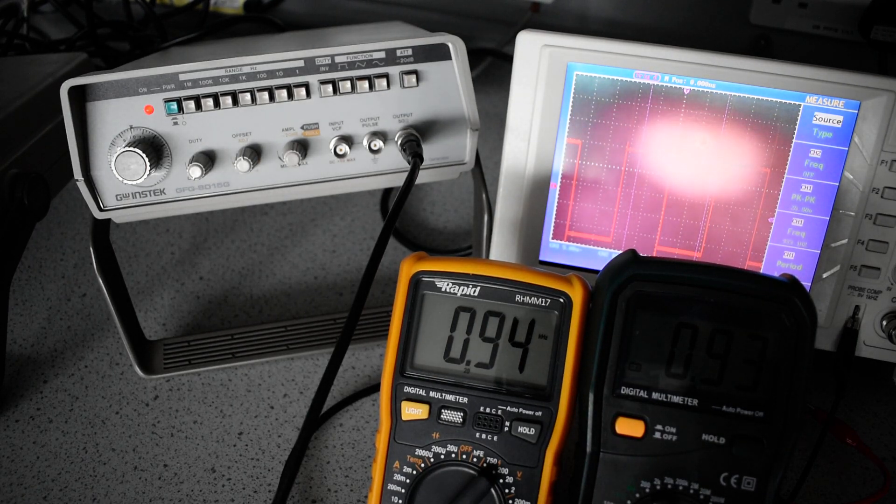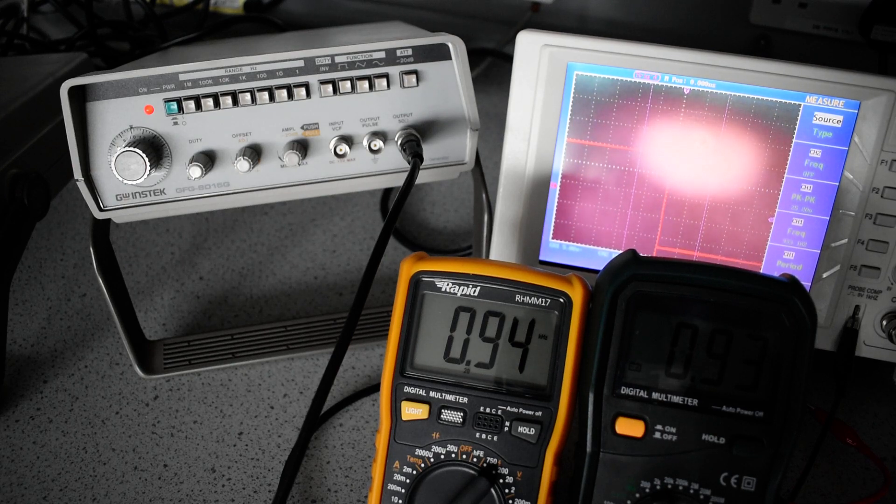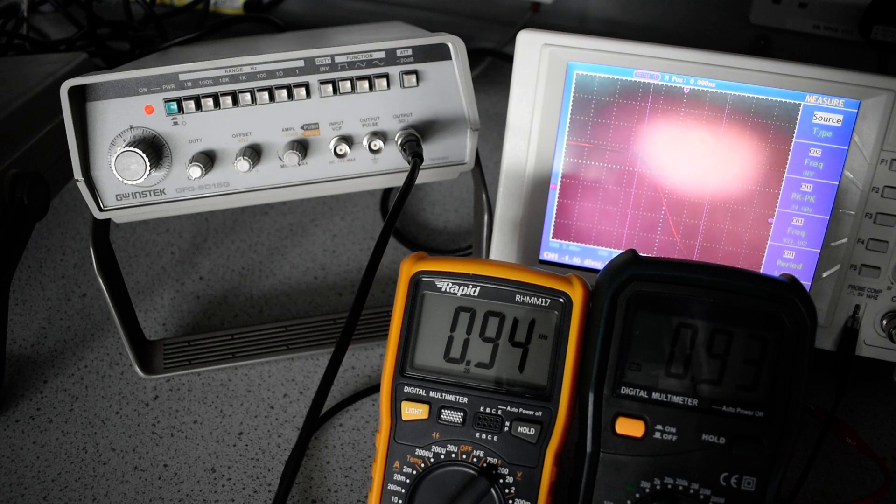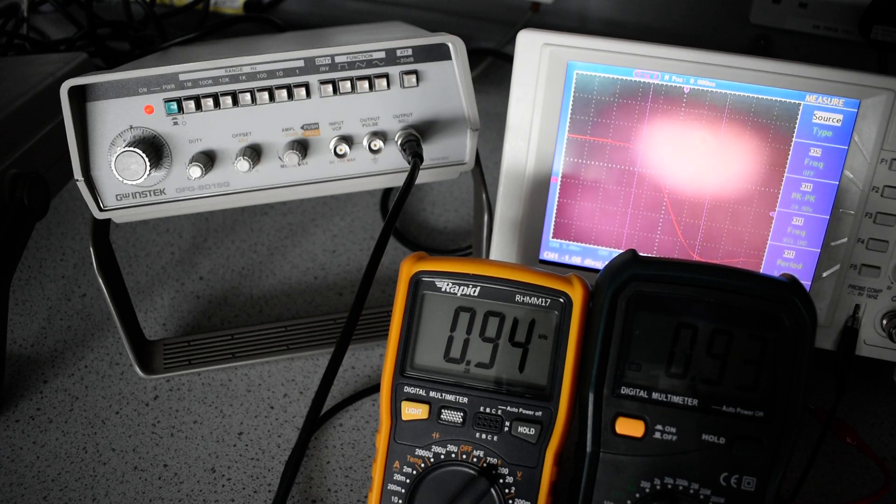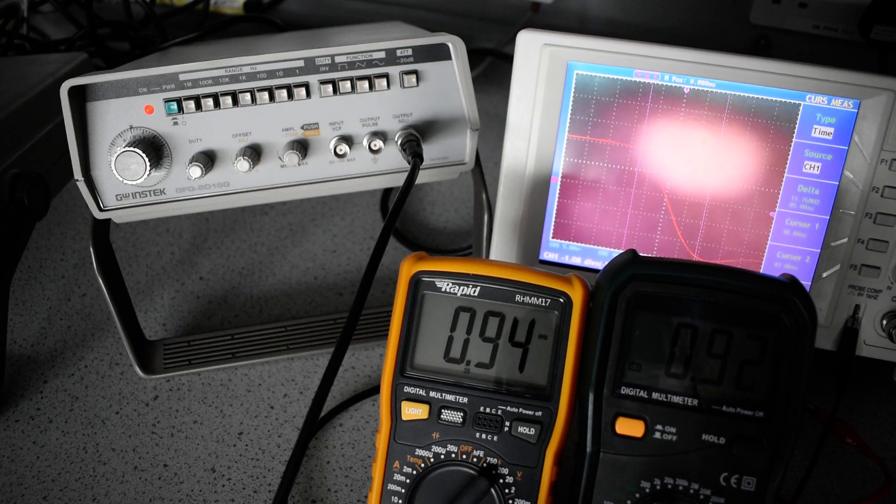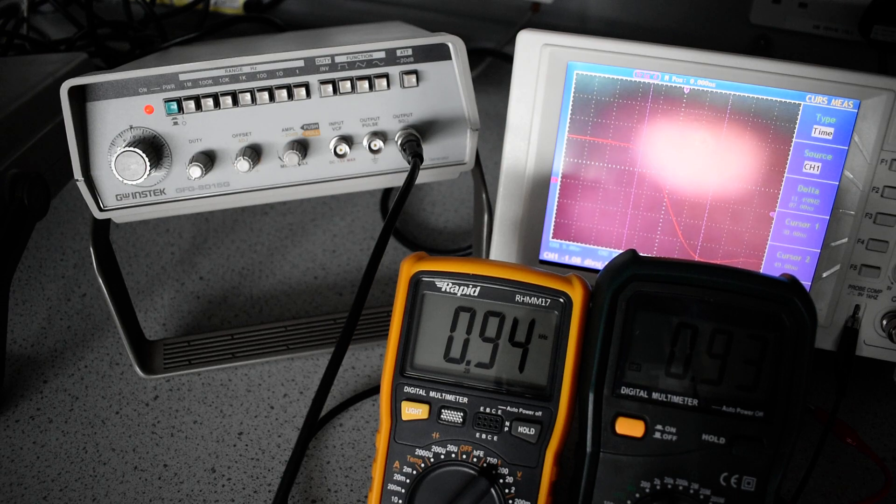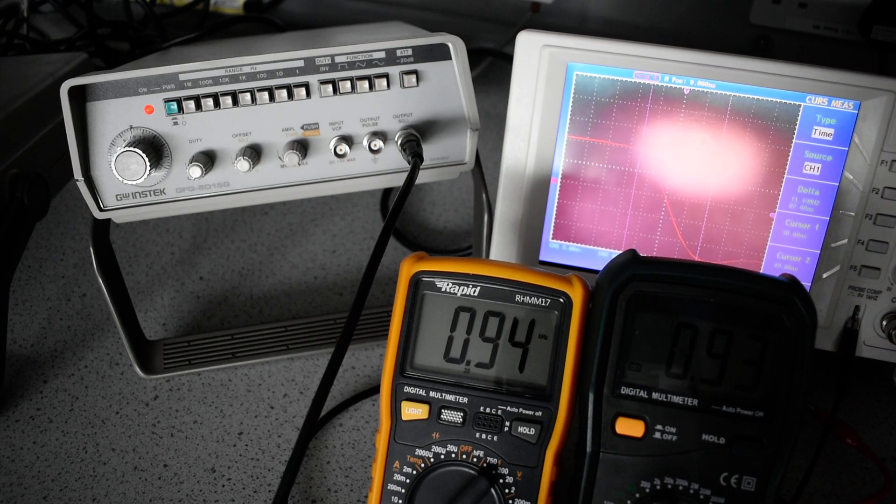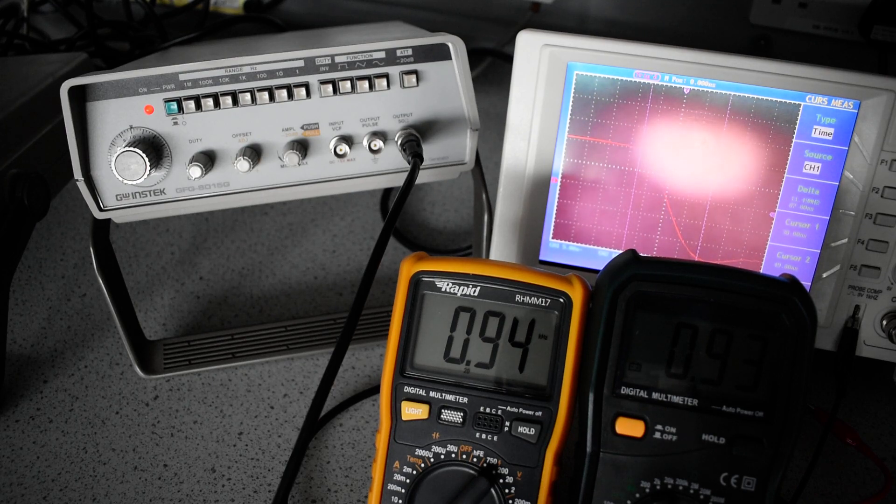If we want to check rise time of signals of a square wave, we can wind the horizontal time base down and we can use the cursors to measure the rise and fall times. If we use those cursors, we can see that we're measuring about 87 nanoseconds for the fall time, which is within spec. It has to be less than 100.